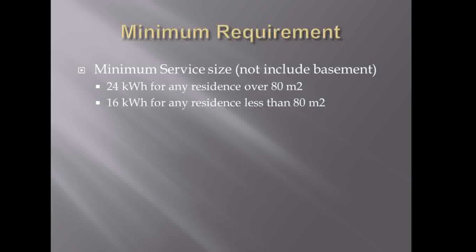Then we talk about the minimum requirement. For a single dwelling not including the basement, if the residence is over 80 square meters above grade, you need a minimum of 24 kilowatts. If it's less than 80 square meters, you need 16 kilowatts.